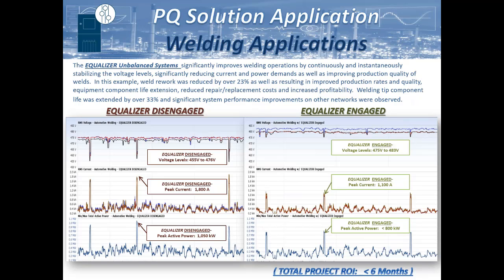So reducing the peak power, reducing the current, all of which actually had a remarkable impact on that production area's performance. So they were able to reduce their rework requirements because we were able to stabilize that voltage and stabilize the current. It made the qualities of the weld much better. And also because we're reducing that current and reducing the amount of heat required for that process, we extended the life of those welding tips by over 33%.